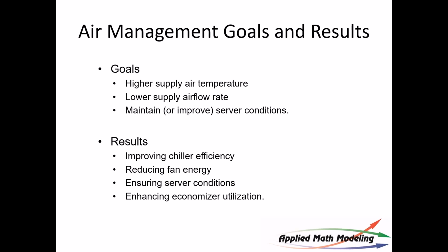A lot of economization going on right now where you're basically taking outdoor air temperature and supplying it to the servers. And we see this in chiller design or cooling design. Sometimes they use evaporative media to do this. Sometimes they're just using dry air heat exchangers. Magnus, I don't see so much what we used to call free air, where they bring the air directly into the data center. I see dry.